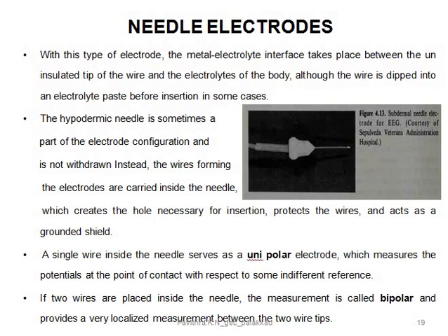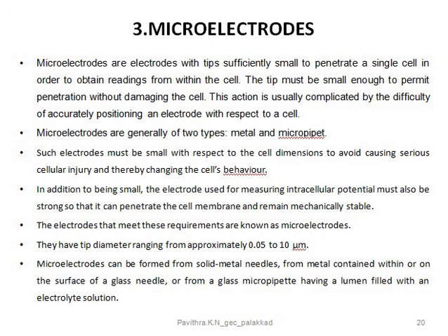Okay, so needle electrodes and other types of electrodes that create an interface beneath the surface of the skin seem to be less susceptible to movement artifacts than surface electrodes, particularly those of the older types. And by making direct contact with the subdermal tissue or the body intercellular fluids, these electrodes may also have lower impedance than the body surface electrode of comparable interface area. That is the difference between the needle electrode and the body surface electrode. Now next, let us move on to the microelectrode.